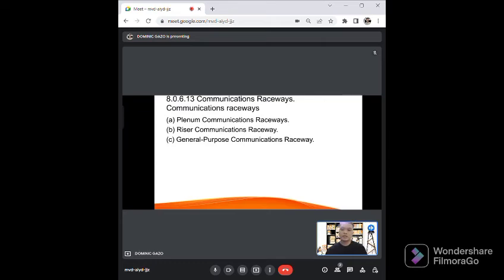And then we have communication raceways for Article 8.6.13, and then for A, plenum communication raceways. These plenum raceways and optical fiber raceways shall be permitted for use in ducts, plenums, and other spaces used for environmental air and shall also be listed as having adequate fire resistance. And then for riser, this riser communication raceway shall be listed as having adequate fire resistance characteristics. And then for general purpose communications raceway, this general purpose communication raceway shall be listed as having adequate fire resistance characteristics.